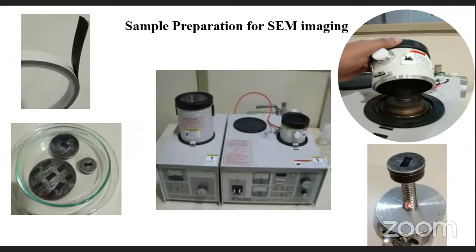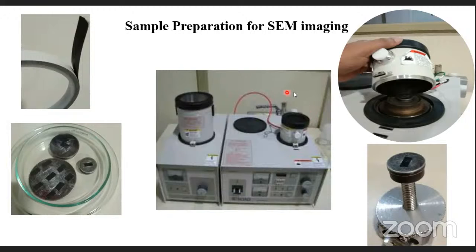We directly place conductive samples into the stub holder and go for analysis. For non-conductive samples, we use the gold sputtering unit — from Hitachi in our case. A very small amount of gold, only one to two nanometers thick, is coated over your sample. It won't disturb or affect your sample morphology. We place the sample inside the chamber, apply vacuum, do the sputtering, then put it on the stub holder for direct analysis.